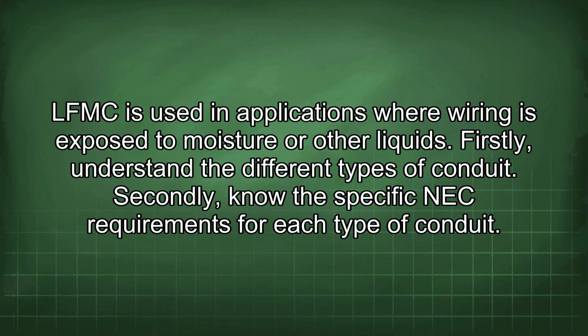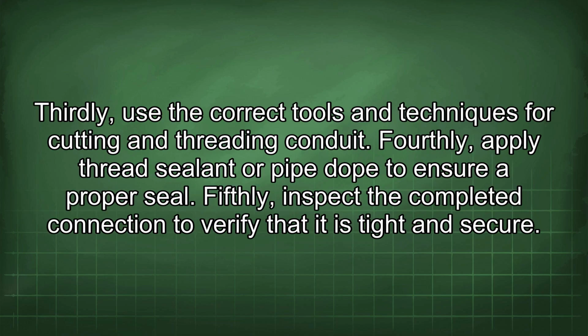Firstly, understand the different types of conduit. Secondly, know the specific NEC requirements for each type of conduit. Thirdly, use the correct tools and techniques for cutting and threading conduit. Fourthly, apply thread sealant or pipe dope to ensure a proper seal. Fifthly, inspect the completed connection to verify that it is tight and secure.